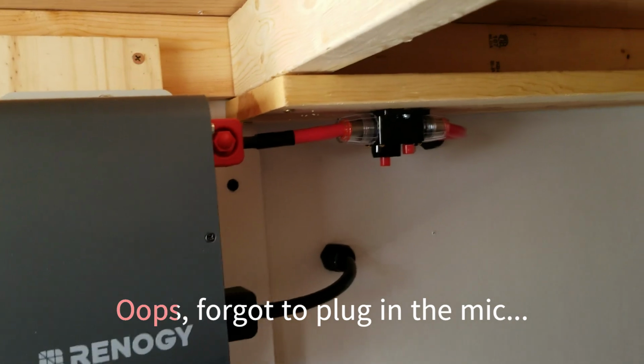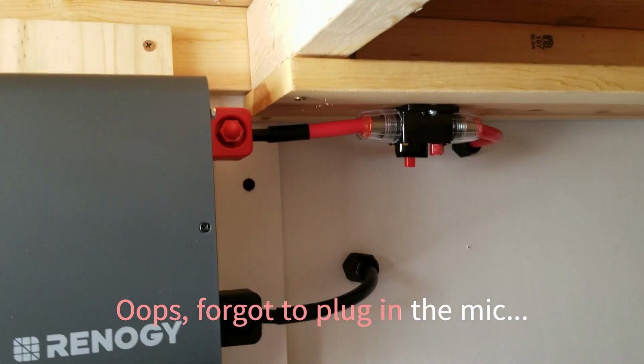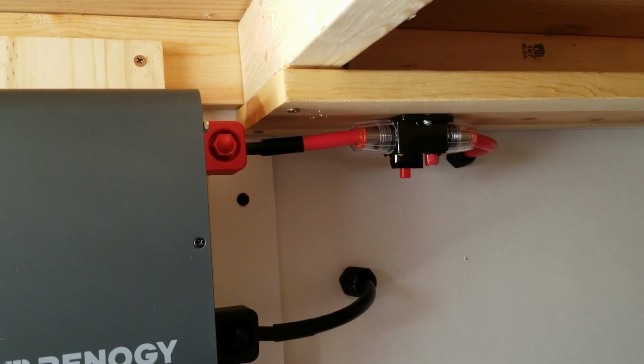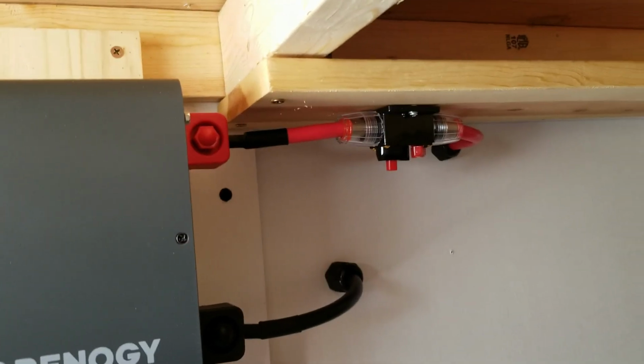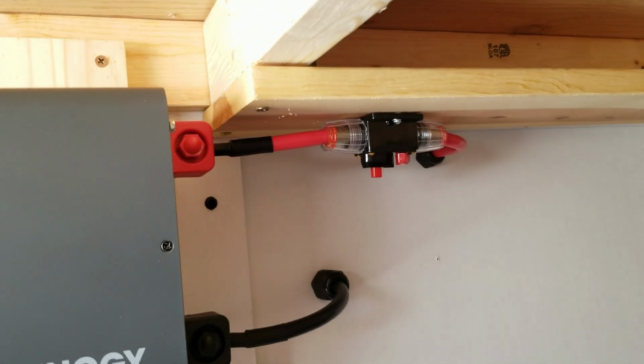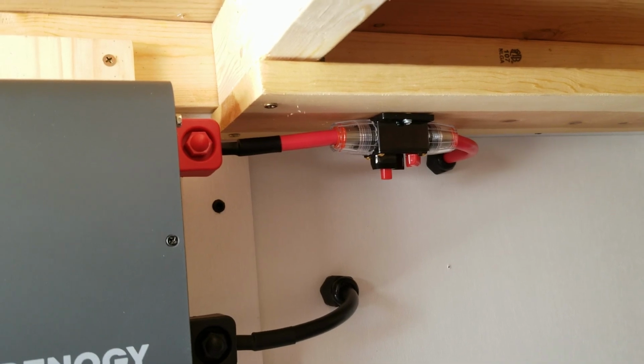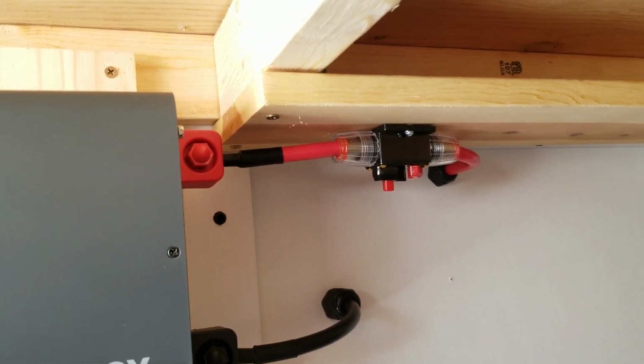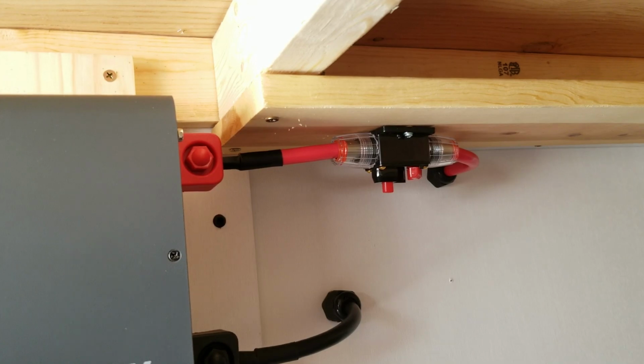Okay, here is the DC side of the inverter. As you can see, I'm putting my battery on the other side of this wall, and I've put in a 150 amp circuit breaker, as that is recommended for this size inverter. Renogy also recommends that the ground on the inverter be tied to the chassis of the vehicle.